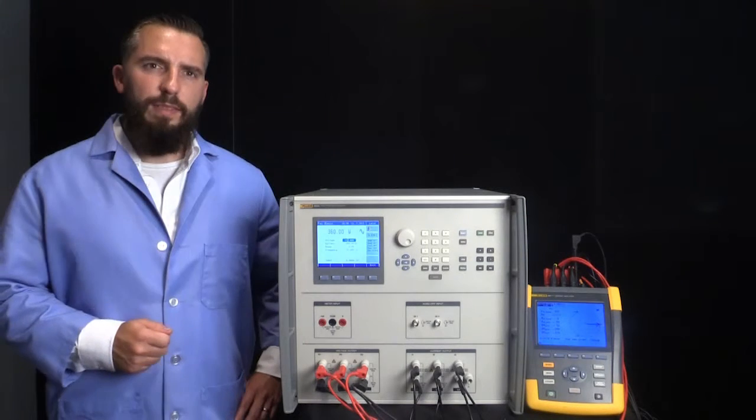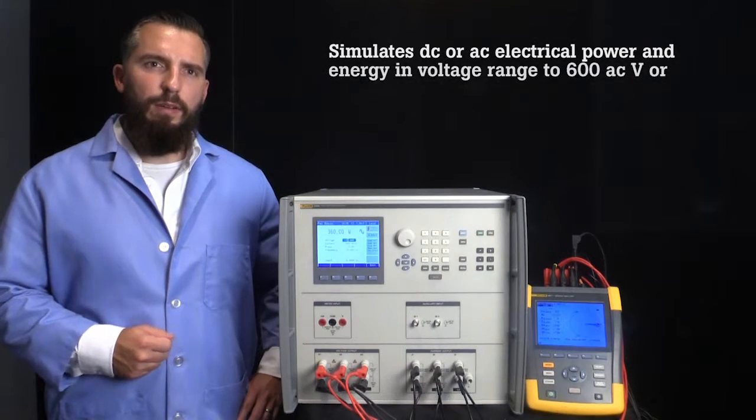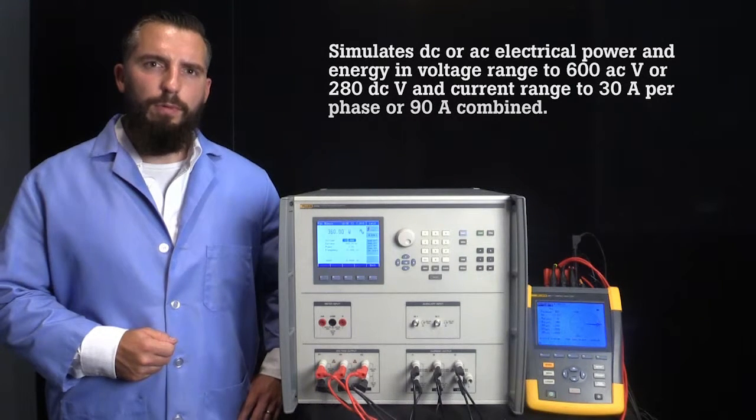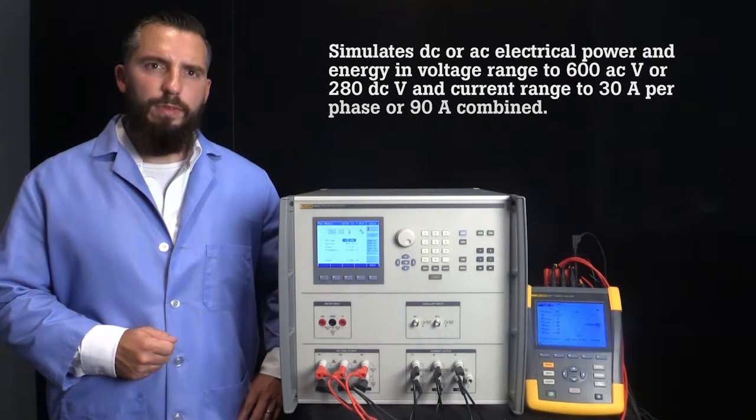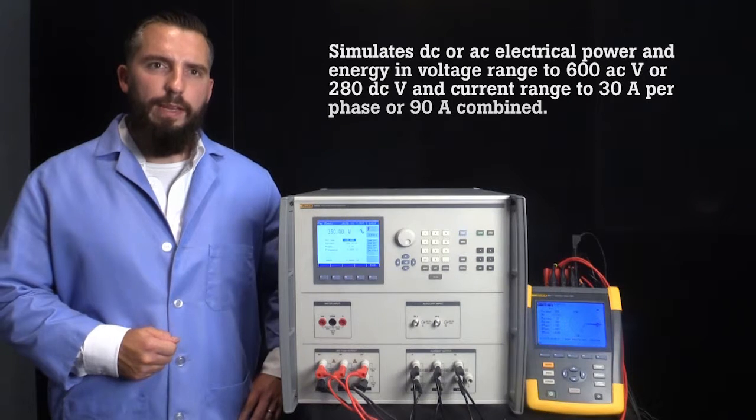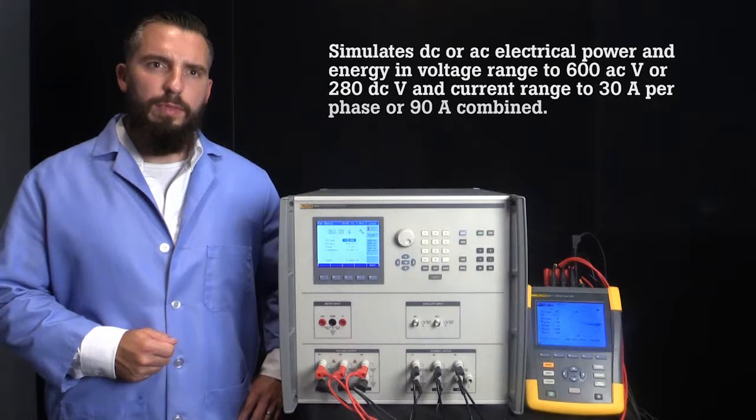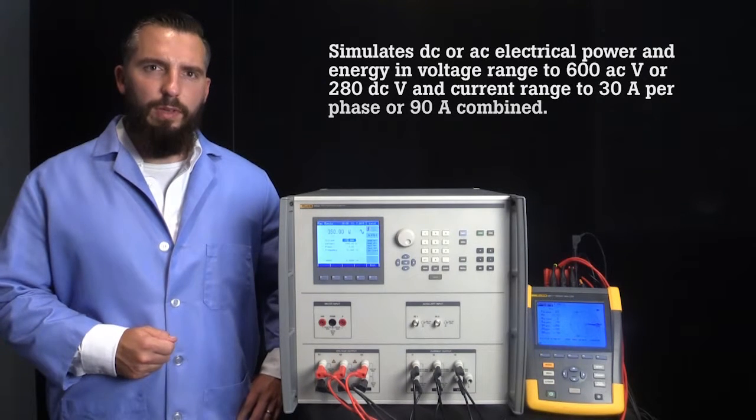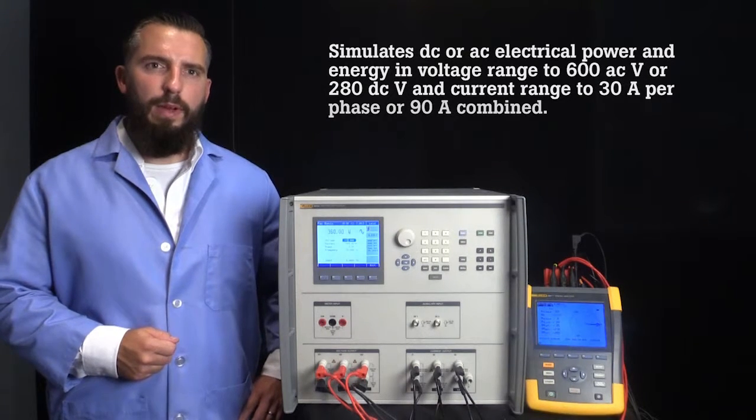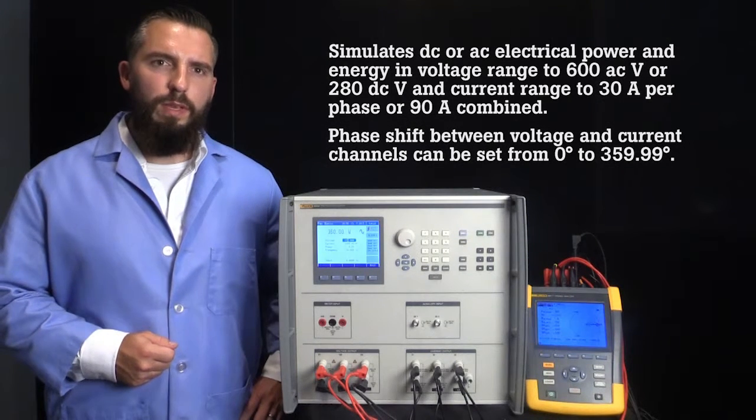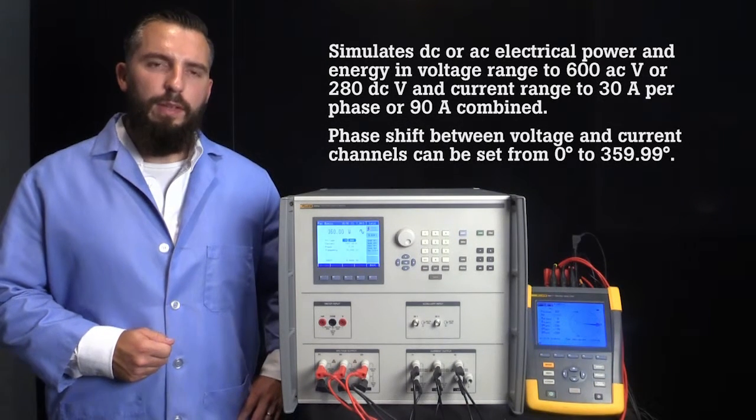The 6003A simulates DC or AC electrical power and energy in voltage ranges from 1 volt to 600 AC volts or 280 DC volts, and current ranges from 8 milliamps to 30 amps per phase, or 90 amps combined into one phase. Phase shift between voltage and current channels can be set from 0 degrees to 359.99 degrees with the best accuracy of 0.01 degree.